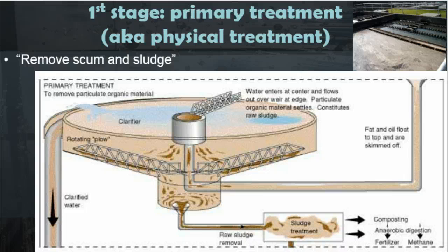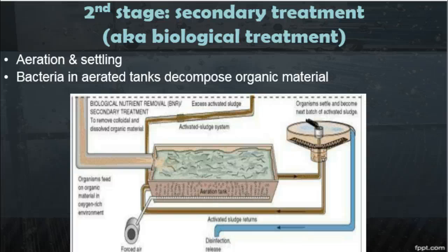And then the primary treatment has, at this point, removed about half of the solids, total organic material, and bacteria. So it's gotten it halfway clean, basically. If the plant doesn't do anything else, then the water is chlorinated at this point to kill the remaining bacteria, and then they let it out into whatever stream it is. So some plants will only do primary treatment. However, a lot of them will also do secondary treatment, which is usually a biological treatment.